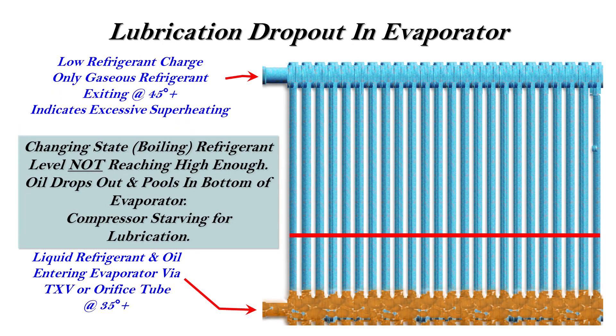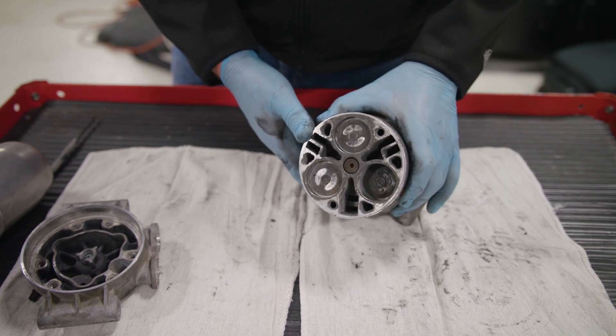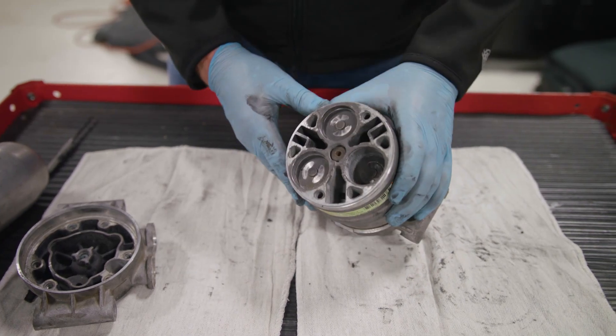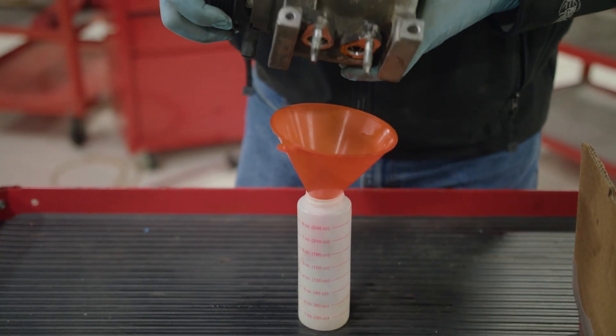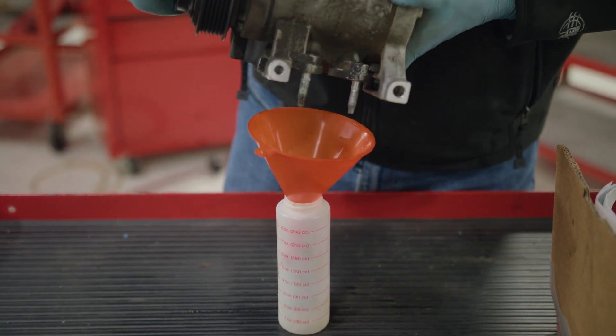If the system is undercharged, the oil, which does not evaporate, separates from the gaseous refrigerant and drops to the bottom of the evaporator. Now only pure refrigerant, which by itself is a powerful degreaser, returns to the compressor. This washes down the vital lubricating film of oil from the compressor pistons and cylinder walls. With no lubrication, the compressor starts to wear and fails rapidly.